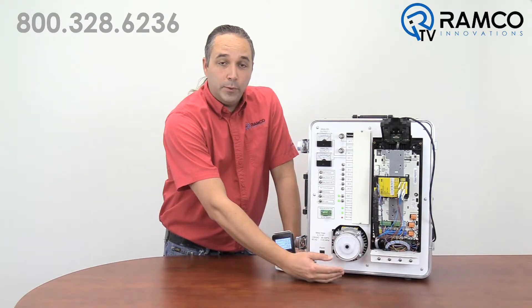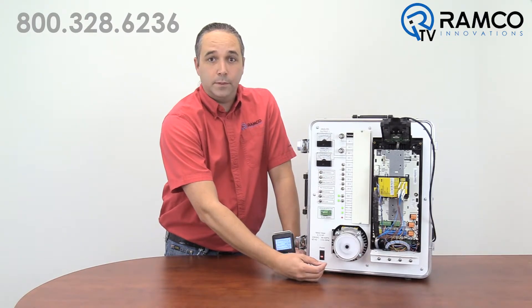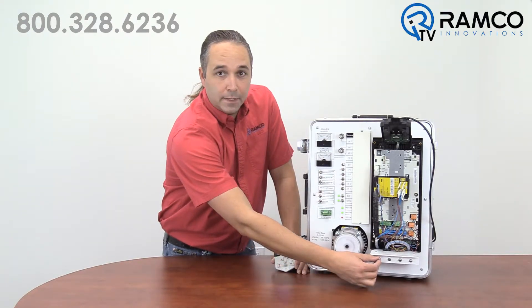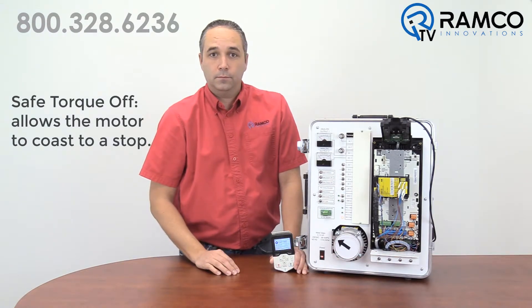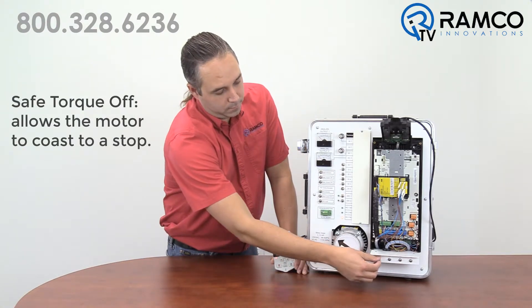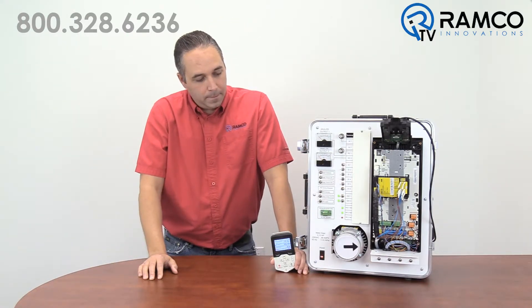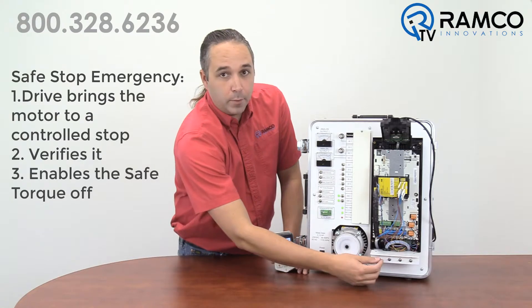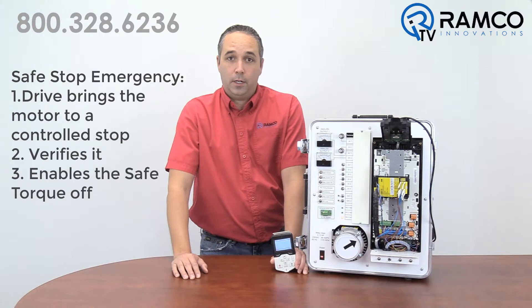I have added four double-pole toggle switches for this demo. I've configured the first two for safe torque off and safe stop emergency. As you can see, the safe torque off input lets the motor coast to a controlled stop. When I do the safe stop emergency, the drive brings the motor to a controlled stop, verifies it, and then enables the safe torque off.